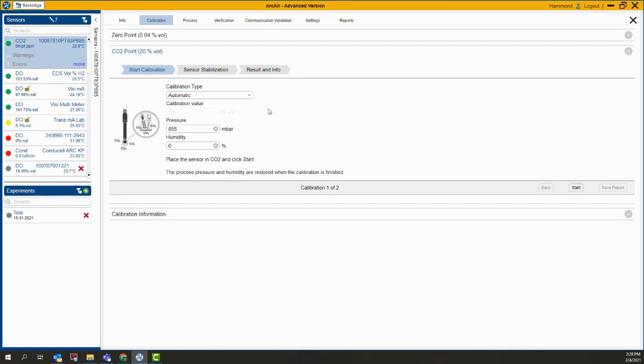The other thing that I would recommend is that you've got pressure and humidity values here. So you want to take and put in the atmospheric pressure at your location. And if you're using calibration gas, generally it's dehumidified, so you can use 0% here. But you want to adjust that if you're using some other value here. So you can start to see my CO2 value starting to trend up here. So I'm going to give it a little bit of time before I actually start my calibration. I like to see it trend up and stabilize. So let's give it a second here.